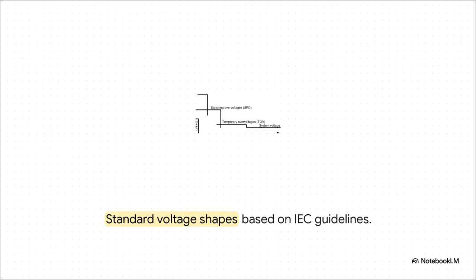Now, what's really interesting about this slide is how we visually classify these standard voltage shapes based on IEC guidelines. You can clearly see the distinct waveforms that differentiate temporary overvoltages, which might last for seconds or minutes, from the sharp, sudden drops and spikes of switching and lightning overvoltages. These standard voltage shapes are precisely what we use to design our withstand tests, basically ensuring our insulators and transformers can actually survive the real world.